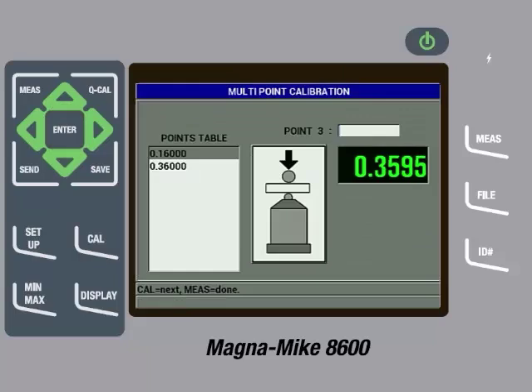The gauge now shows the thin and thick calibration points we have already entered, and it is asking for the next calibration point. At this point, we can add in the other reference standards from the calibration kit that we have not yet entered. We can remove the thick shim fixture. We can then take out the 86D Cal-010 reference standard. Then we will insert the disc into the slot on the top cap and place the fixture on the probe and pull down gently on the calibration fixture.